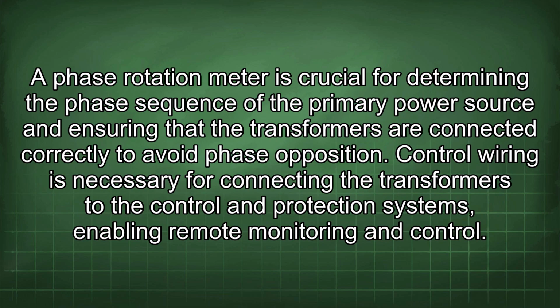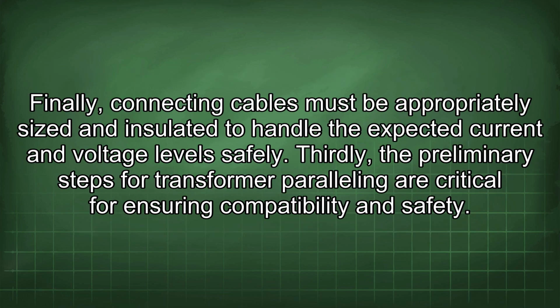A phase rotation meter is crucial for determining the phase sequence of the primary power source and ensuring that the transformers are connected correctly to avoid phase opposition. Control wiring is necessary for connecting the transformers to the control and protection systems, enabling remote monitoring and control. Finally, connecting cables must be appropriately sized and insulated to handle the expected current and voltage levels safely.